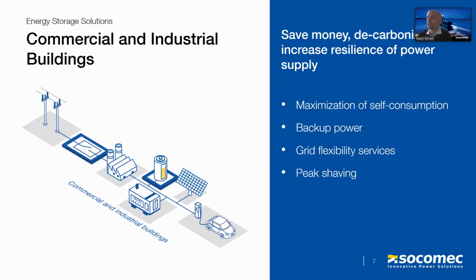So what are the advantages to customers for installing a battery energy storage system in a commercial or an industrial building? So ultimately, we're looking to help to save money, to decarbonize, and to increase the resilience of our power supplies. So you can see here our battery energy storage system is deployed on the customer side. So it is behind the meter, installed within the customer building. Some of the advantages for this could be to help maximize your self-consumption, so to actually consume your energy on site as opposed to exporting it back to the grid. We can provide backup power services, so in the event of mains failure, to be able to continue to supply the building via our battery storage system.